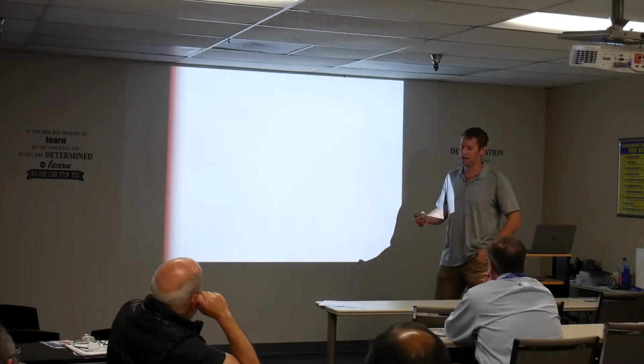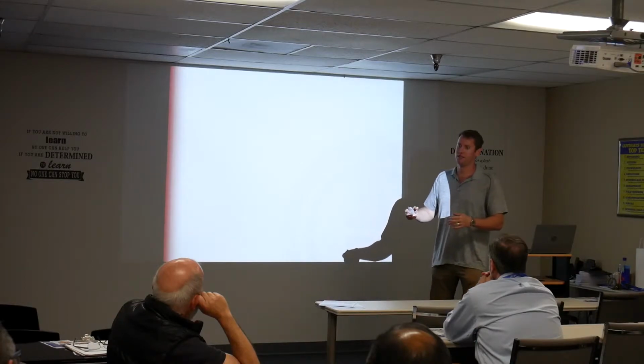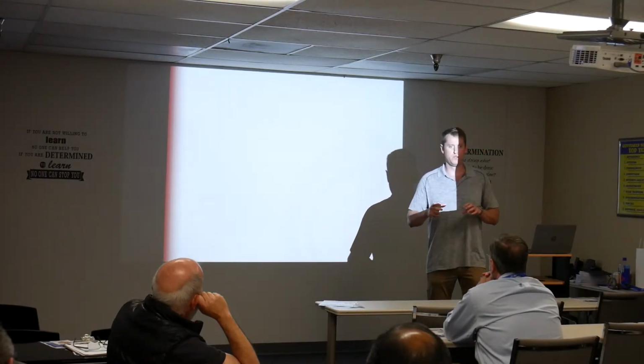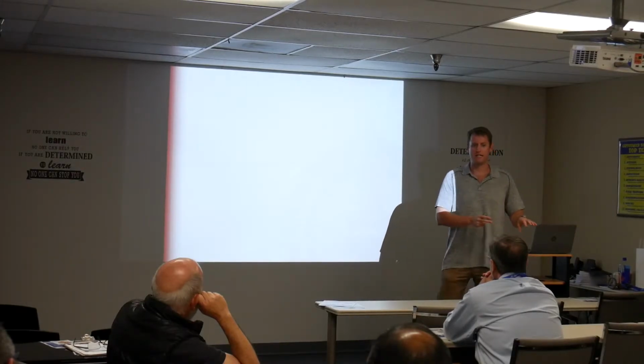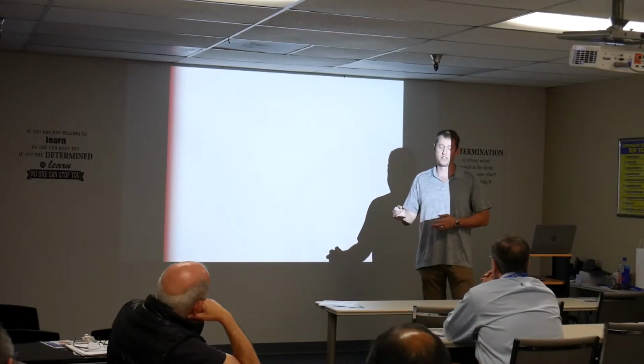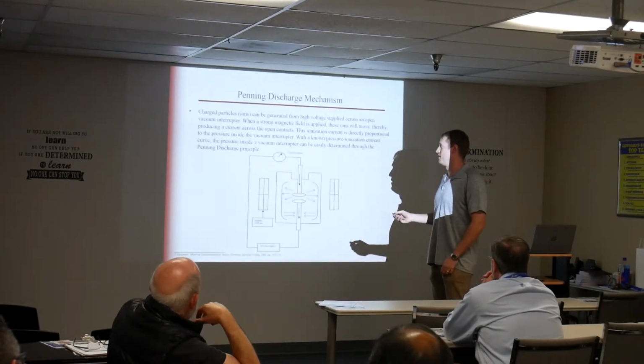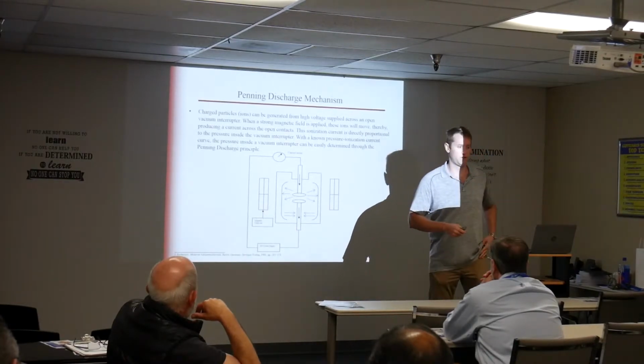My boss went to the GE factory in Burlington, Iowa, and saw that they had a way of doing this. Like I said, we have breaker shops all over the U.S. You send us a vacuum breaker, we high pot the bottles. If the bottles are good, we rebuild the breaker and stick those same bottles back in it. The last thing we want to do is send you a breaker that a year later the bottles fail and it comes back onto us. So that's why we use this within our own company for 10 years.